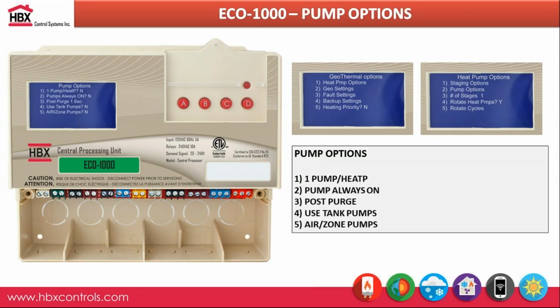So you can customize both of when you want to turn on and when you want to turn off within those options as well. In terms of pump control, you have the option to make the controller itself control the pumps. There's a lot of units within the heat pumps that'll operate on their own. So you would just tell the controller that, hey, I want to control the main circulating pumps within the 1000 as well. Again, we have post purge up on there from 1 second up to, I think, 500 seconds. In terms of post purge, you can have your pumps running all the time if you really wanted to, even though you don't have a heating or cooling demand on there.